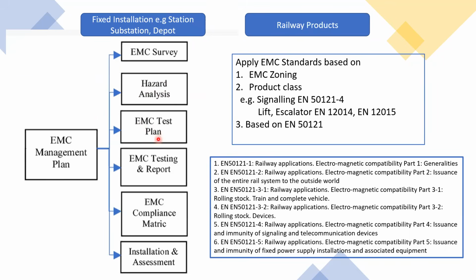We will prepare an EMC test plan and test on site to ensure the levels of electromagnetic radiation outside the railway premises are within acceptable levels. We produce EMC compliance matrix which ensure all products used inside the station, substation, or depot comply with relevant EMI standards, like EN 50121 or 61000-6 series standards. There is also a requirement to ensure installation of the equipment is done according to standards like 61000-5-2, which makes sure cables are routed properly without creating big interference.